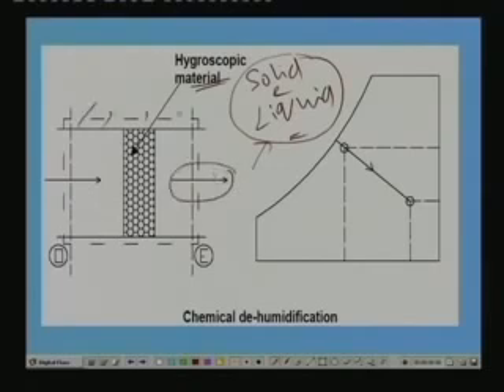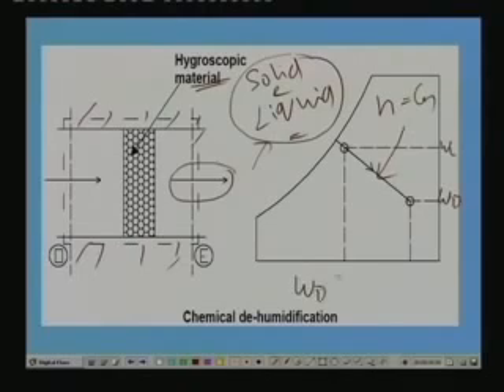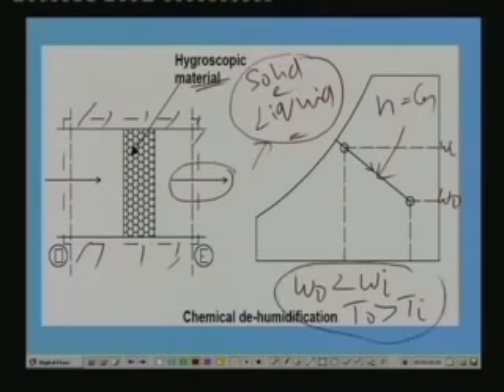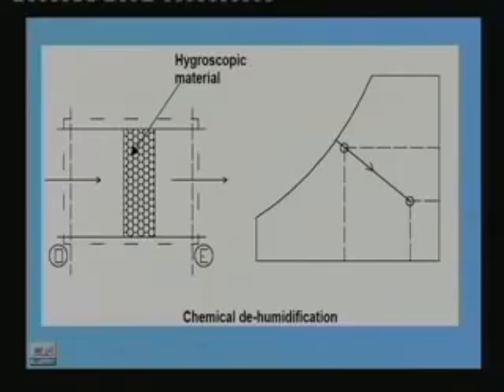And if you assume that this process is taking place adiabatically, that means everything is perfectly insulated, then this process will take place along a constant enthalpy line, that means enthalpy remains constant. You can see that during this process, between inlet and outlet, the humidity ratio is reducing. At the same time the temperature is increasing, that means To is greater than Ti. So, this is the example of chemical dehumidification or heating and dehumidification process.